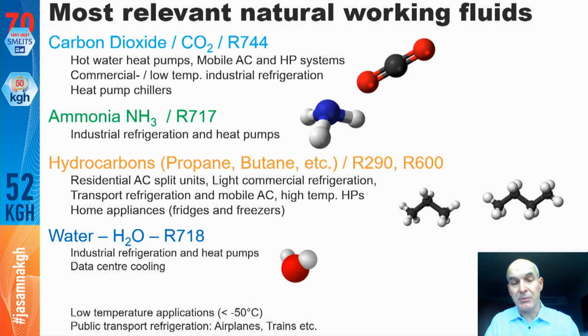We see some high temperature heat pumps where we can utilize the properties of both butane and propane very well, achieving 120 to 130 degrees C, which is necessary in some applications where we have to reheat very hot water to sterilize and similar tasks.